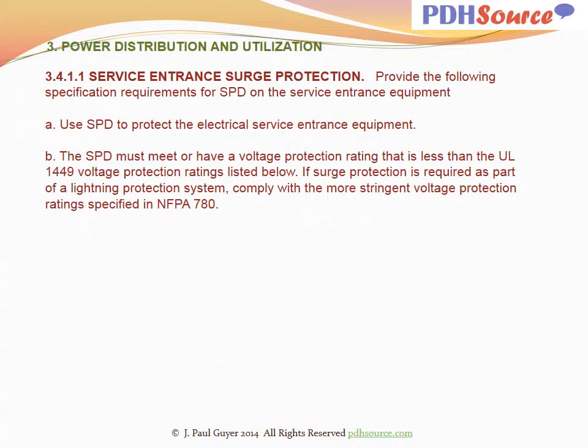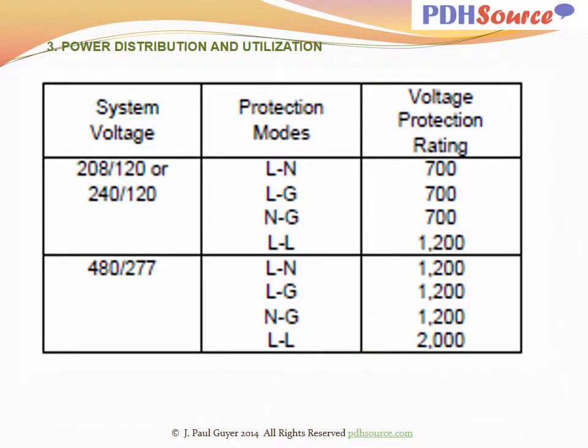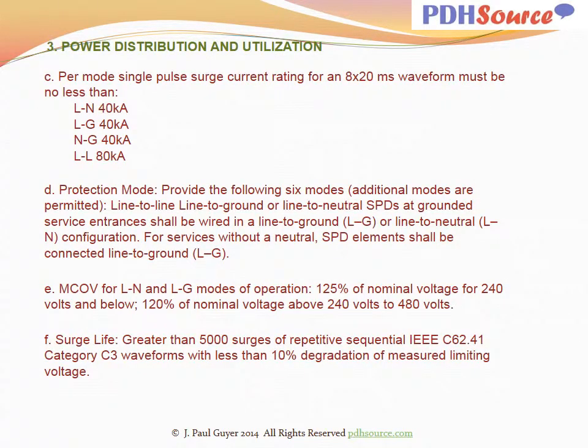If surge protection is required as part of a lightning protection system, comply with the more stringent voltage protection ratings specified in NFPA 780. This table indicates the system voltage protection modes and voltage protection rating requirements. Per mode, single pulse surge current rating for an 8x20 µs waveform must be no less than LN 40 kA, LG 40, NG 40, LL 80.